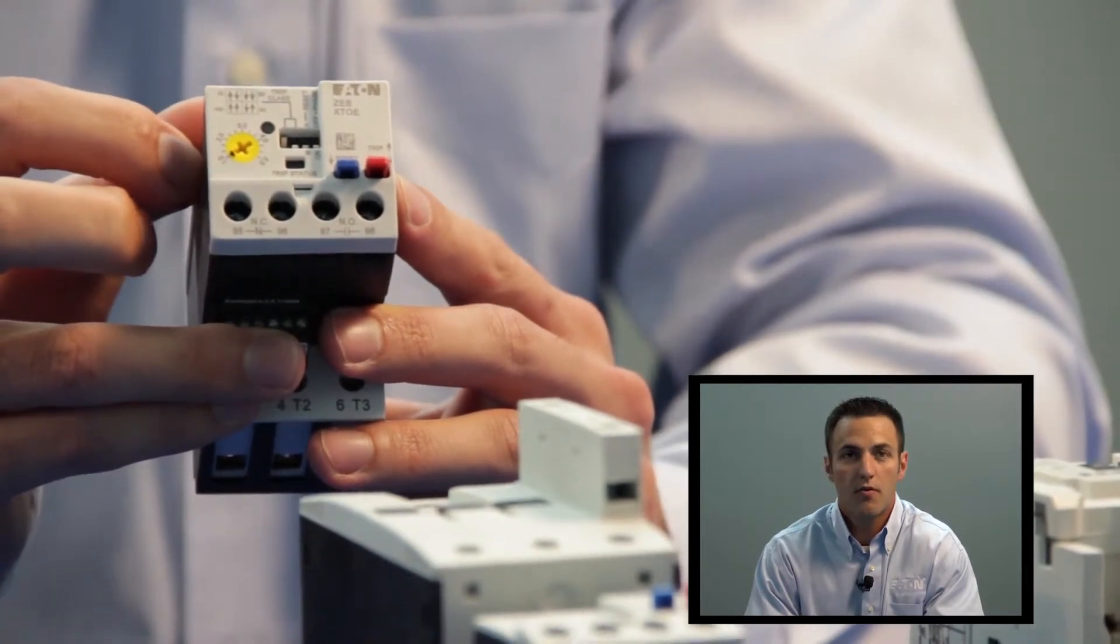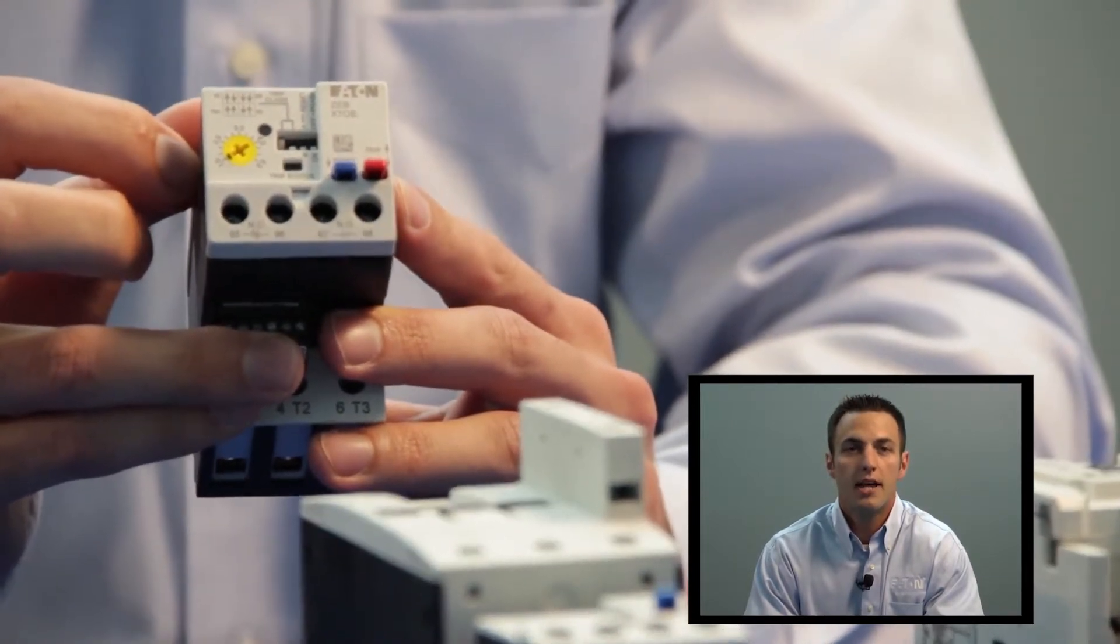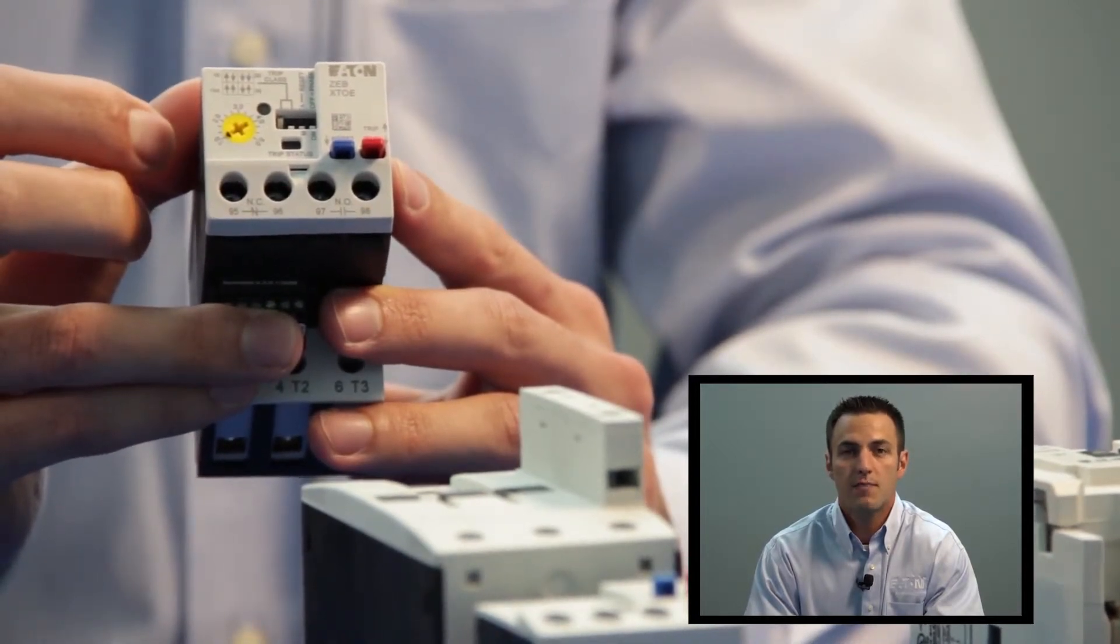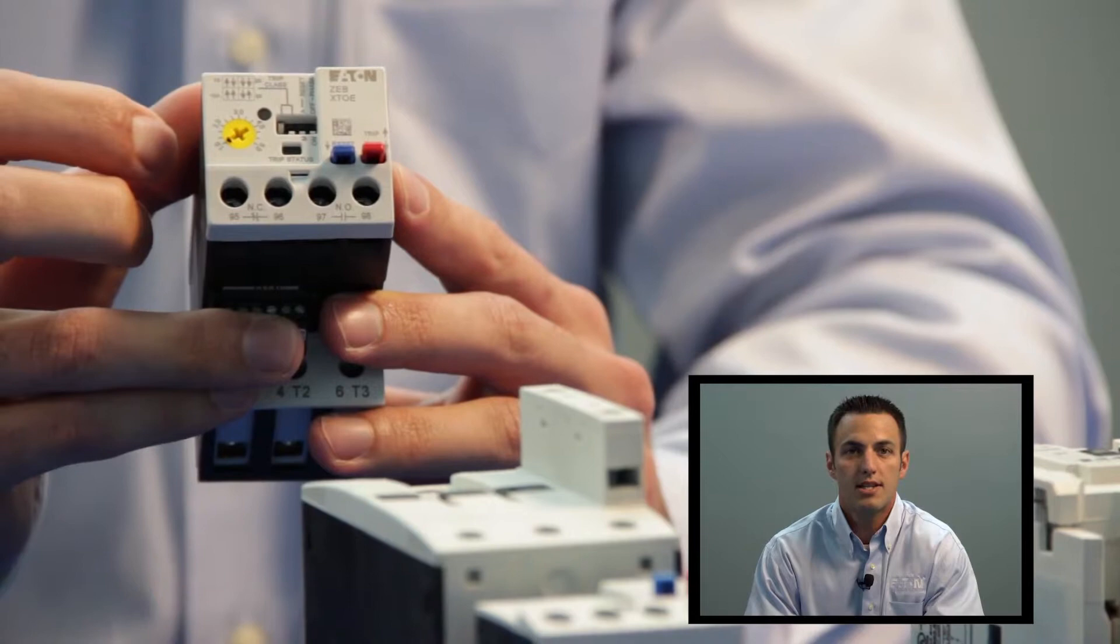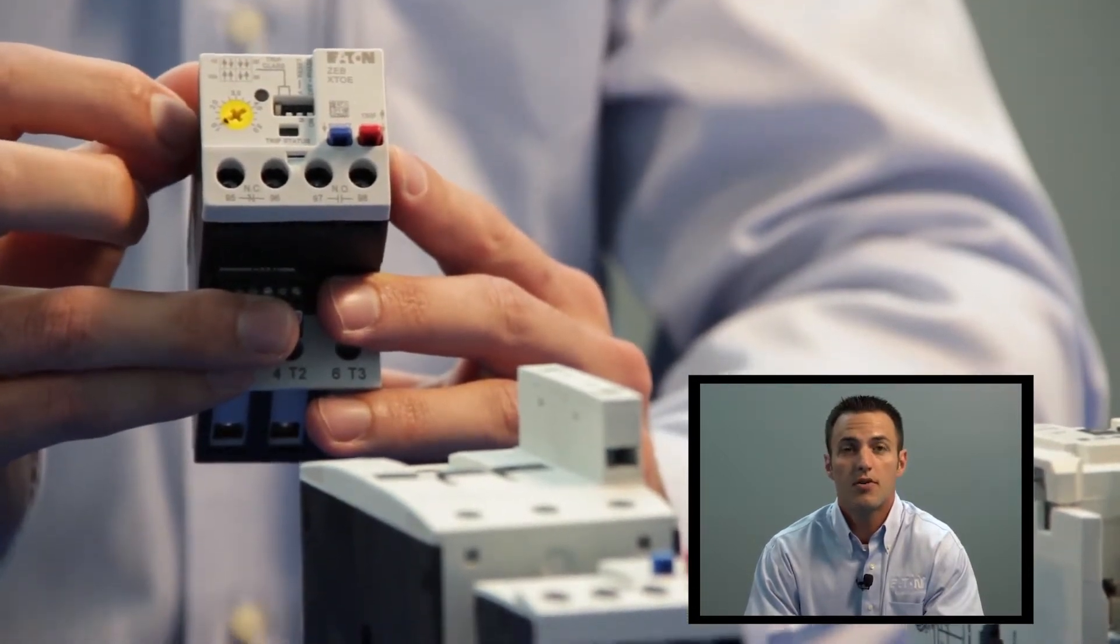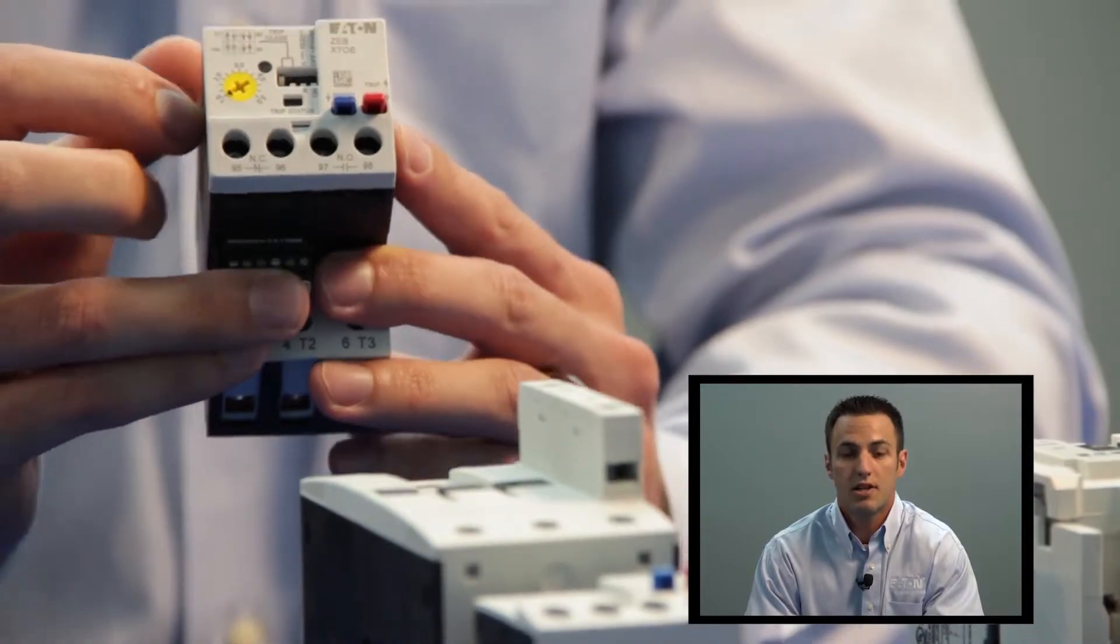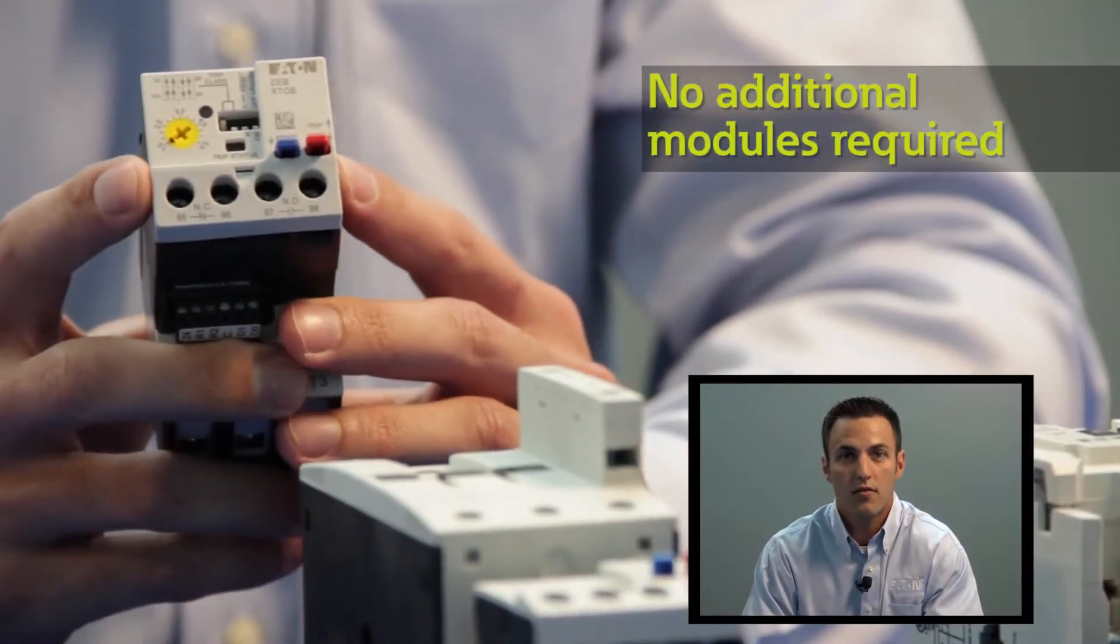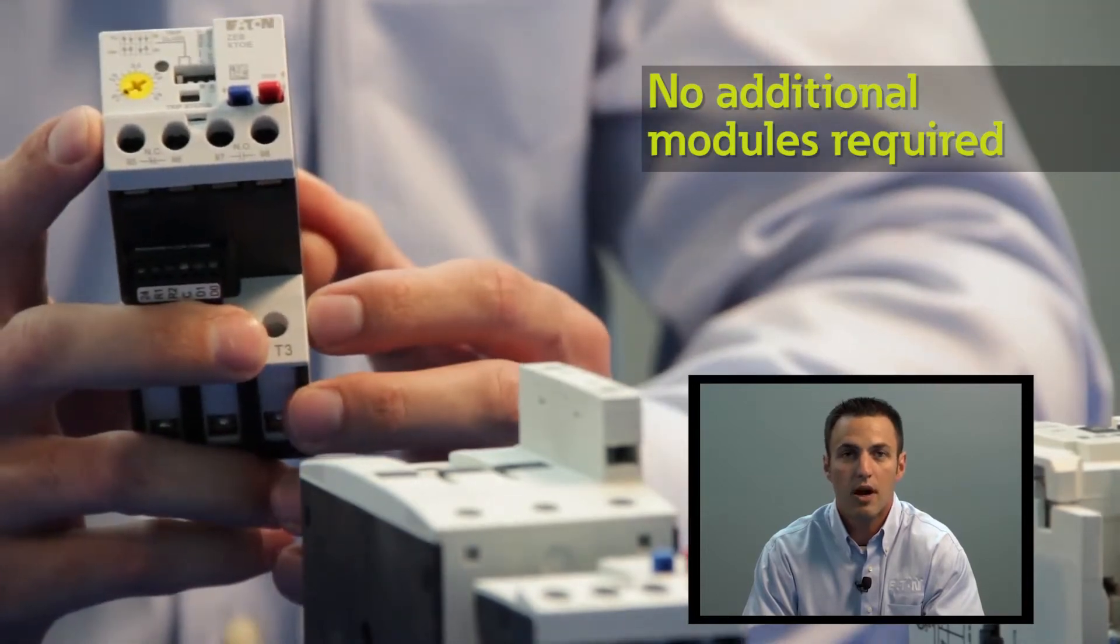The first two dip switches allow you to set the motor trip class. Options are available for class 10A, 10, 20, and 30. The third dip switch is used to select between manual and automatic reset, and the fourth dip switch is used to enable or disable the internal phase imbalance protection. No additional modules are needed for that feature. It's built right into the overload, so there's no snap-on module required for phase imbalance.